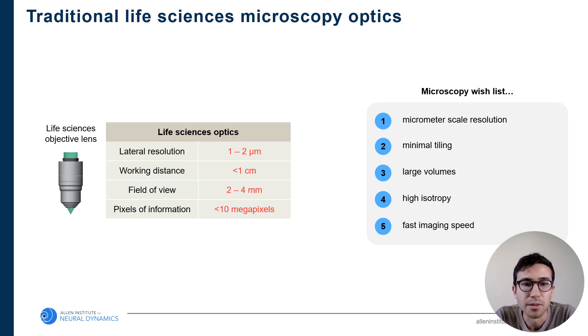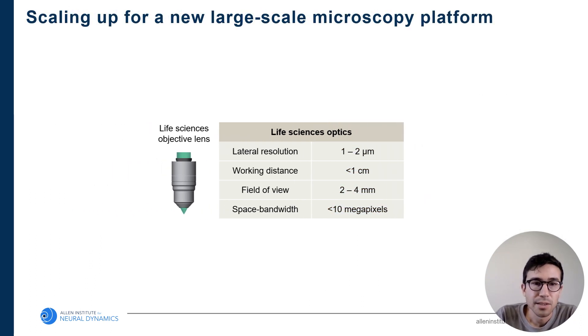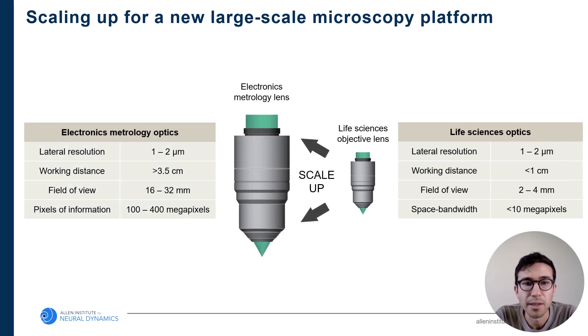When you look at life science optics from all the vendors, their offerings fall into a similar spec range: if you want a lateral resolution of a few microns, the working distance is probably less than a centimeter, the field of view will be a few millimeters, and when paired with a camera, the number of pixels of information captured is probably less than 10 megapixels. In this new system, we've decided to not just scale up the brain through expansion, but also scale up the imaging system by choosing new lenses from the electronics metrology space. When you look at the optics available in that industry, they have tremendous specifications — for the same resolution of one to two microns, the working distances can be several centimeters, the fields of view can also be several centimeters, and the amount of information transmitted to the camera is on the order of hundreds of megapixels.